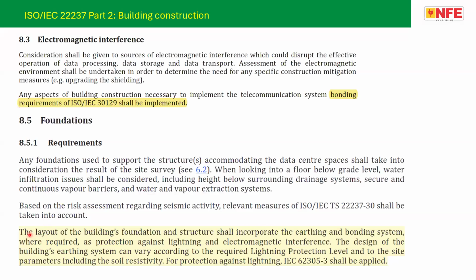Foundation during construction, 8.5.1. The layout of buildings, foundation and structure shall incorporate, please note, shall, not should, incorporate the earthing and bonding system. That means you must do the earthing and bonding in the foundation of the building. Where required as protection against lightning and electromagnetic interference, the design of the building's earthing system can vary according to the required lightning protection level and to site parameters including soil resistivity. So for protection against lightning, this particular IEC 62305 shall be applied. So these are, wherever, as I said, the shall is there, these also must be maintained.